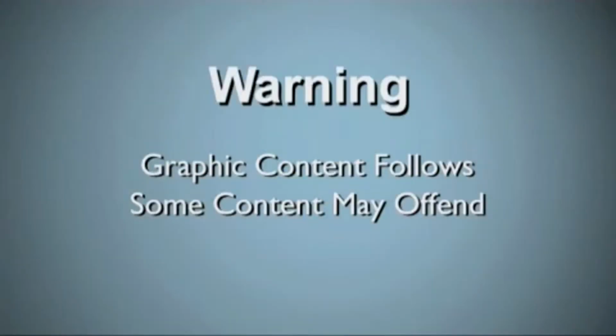The following is actual security camera footage to help communicate the seriousness of arc events. Sensitive viewers may find it disturbing and may wish to look away. In this example, a site engineer is racking in a circuit breaker without protection from the arc fault. Notice the rear of the cabinet for damage.